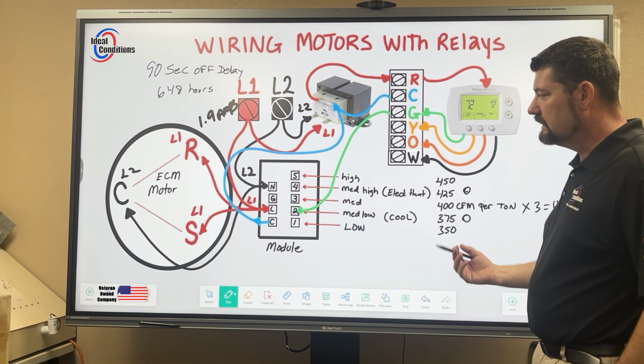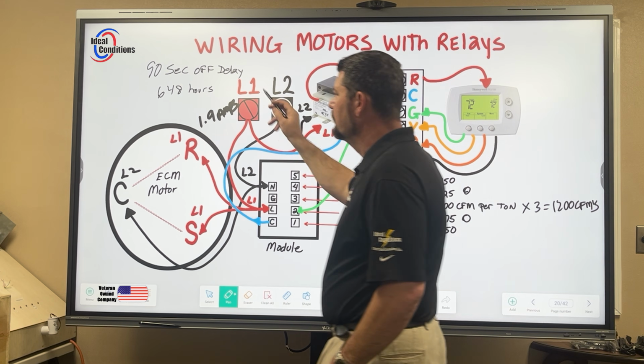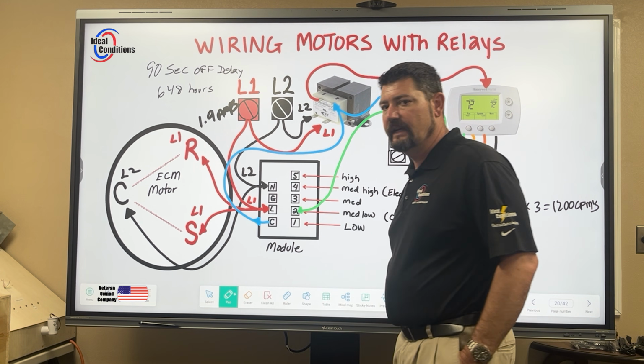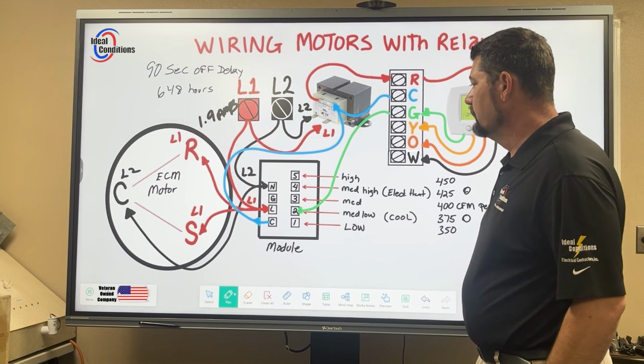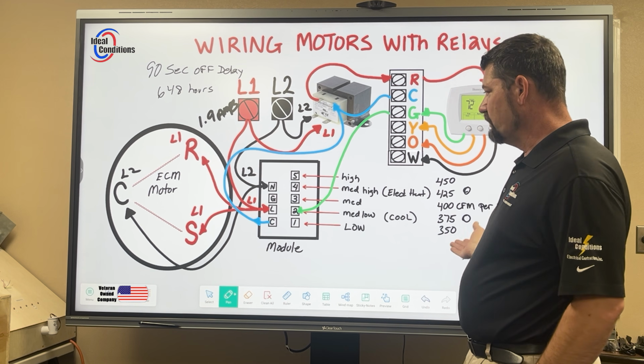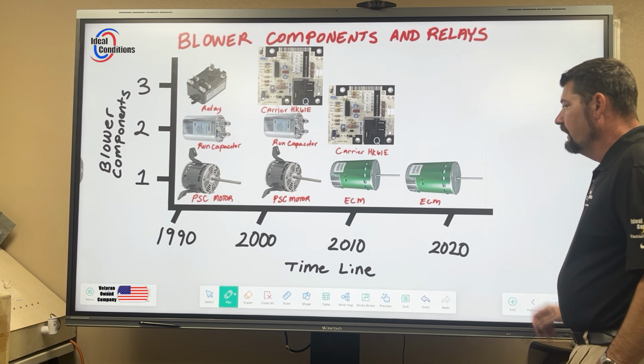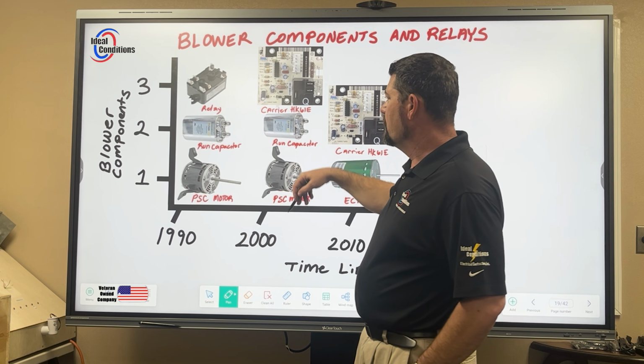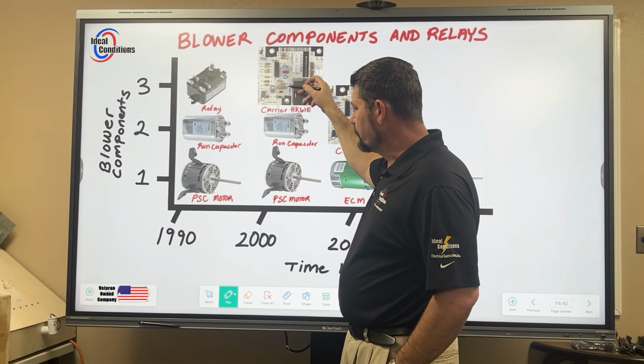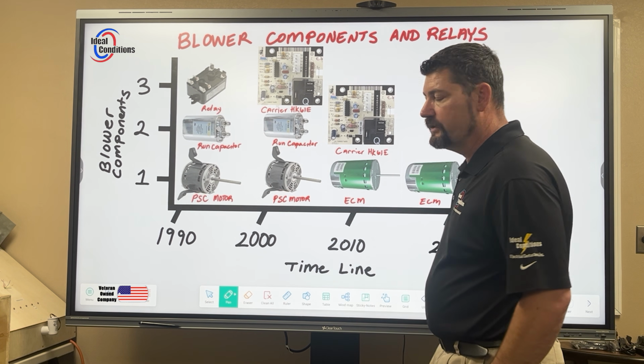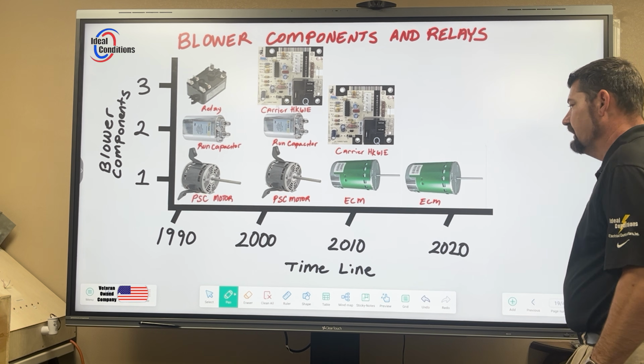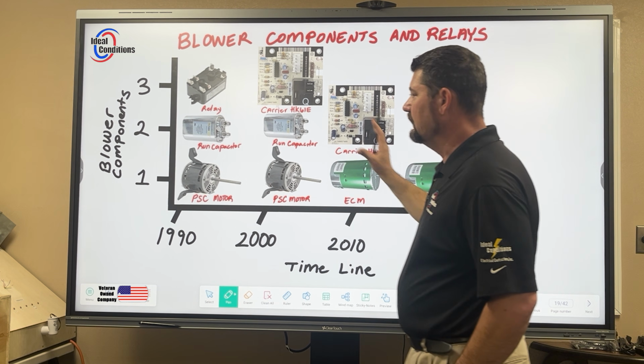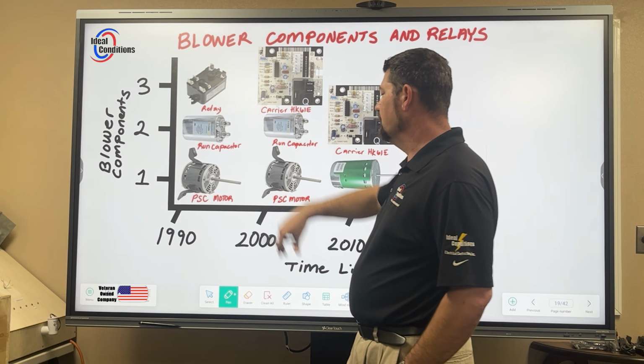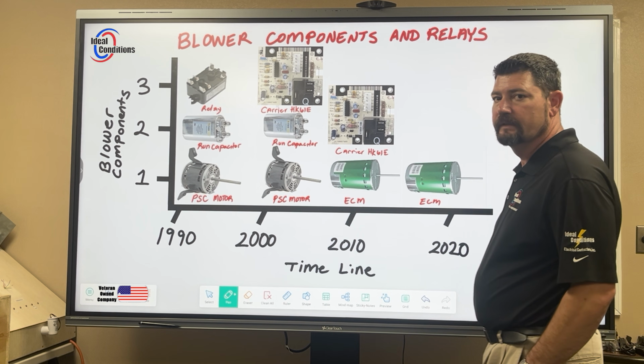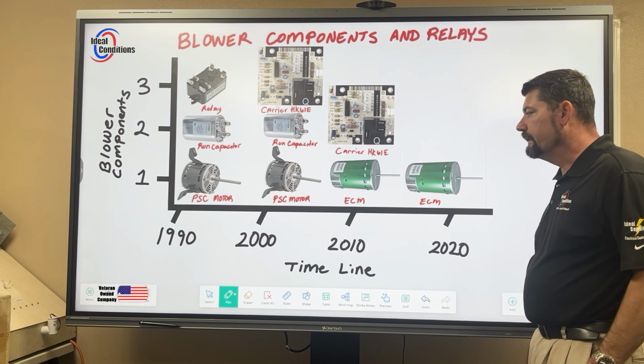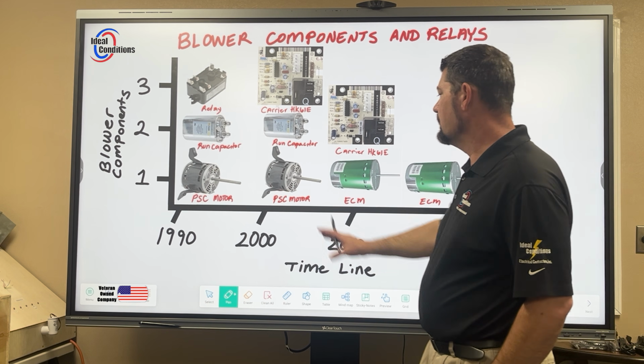But a lot of the times our modules go bad because they don't shut off or they don't activate, and there's not a relay you can replace. And so a lot of times we have to go back down that timeline and put in a PSC motor, integrate either a relay or a blower control board, and put a capacitor in to get that customer back up and running. That's just what we have to do. We talk about that a lot. That's why we cover so much of these PSC motors. You can't get rid of them. They're always going to be there. And they're an affordable truck stock item in comparison to an ECM motor.